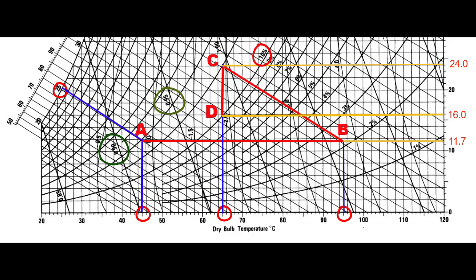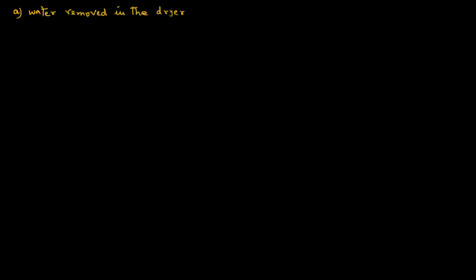We will use these values to make calculations for part A and part B. First we want to determine the water removed in the dryer, which is the B to C process. The humidity ratios are 11.7 for B and 24 for C, so the water removed in the dryer is 24 minus 11.7, which equals 12.3 grams of water per kilogram of dry air.